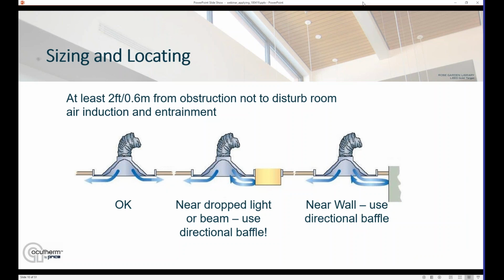Something that is unique to Therma-Fuser diffusers is because we have a thermostat built into the diffuser, you want to make sure that there's no obstructions near the diffuser that could reflect the supply air directly back onto that thermostat. We do use a positive induction mechanism to draw room air up into the diffuser. That's a subject of another webinar, but just keep in mind that no obstructions near the diffuser. So a minimum distance of 2 feet away with a wall or a beam or a light to prevent that supply air from bouncing right back up into the diffuser and throwing off the room temperature measurement. If you do have to locate the diffuser near a wall or a beam or something, we do have directional baffles that can be put in to block flow from one side of the diffuser or two sides, or even like corner arrangements. So if you do have to squeeze that diffuser into a tight space, it's just a matter of getting some directional baffles and blocking the air on the sides where the obstructions are.